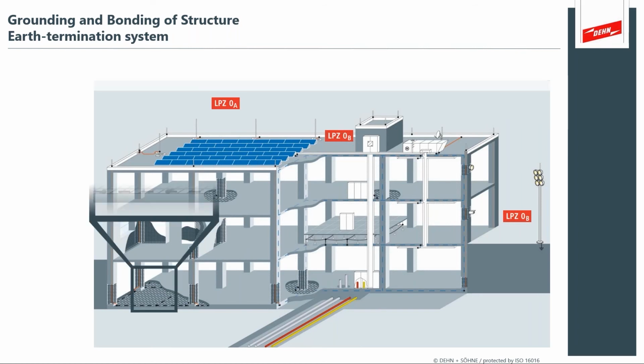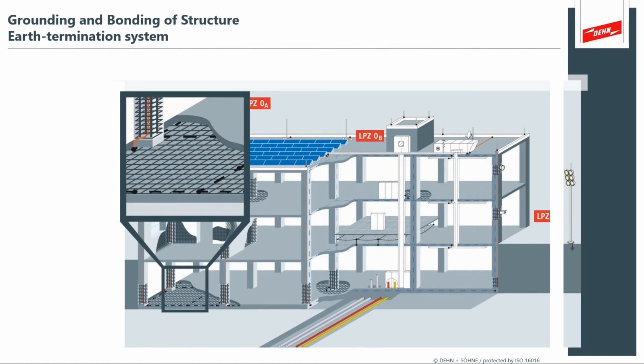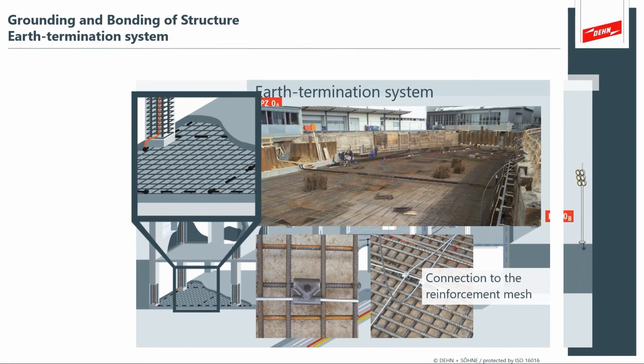So we'll look at the earth termination system also bonded into the actual floor structure and the concrete around the building and embedded in the concrete floor. So this is all part of grounding, bonding of the structure with the earth termination system. And you can see that it would be a well-connected system with dedicated conductors and connections for the purpose of lightning protection that will prevent that arc and spark that you might get in a system that's only casually bonded.